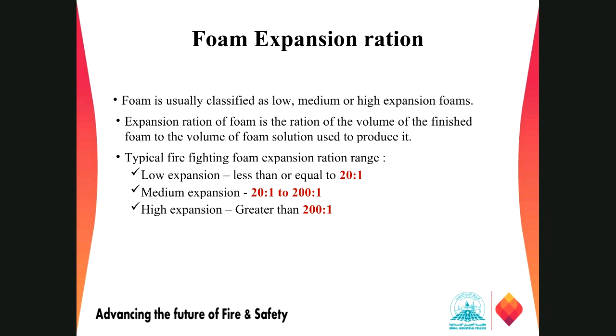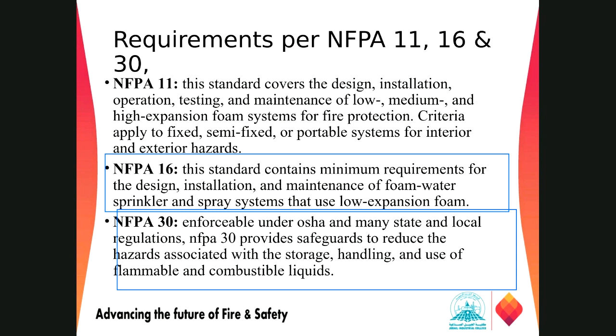So NFPA 11 is a standard which covers the design, installation, operation, testing, and maintenance of low, medium, and high expansion foam for fire protection criteria for fixed, semi-fixed, or portable systems for interior and exterior hazards, right? NFPA 16 is only for foam water sprinkler systems, which is mainly based on the sprinkler system. And NFPA 30 is the one which is the enforceable code, right? So this is the code which tells us about liquids based on their classification, class 1 liquid, class 1A, class 1B, and all those, based on the flash point and the boiling point. It will only tell which area requires foam system protection, and then we have to refer to NFPA 11 and 16 for the installation in the various parts of those occupancies.